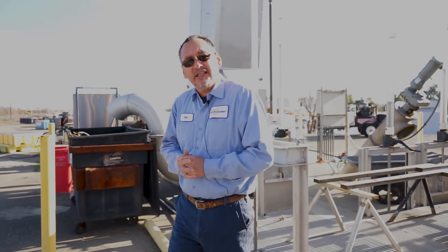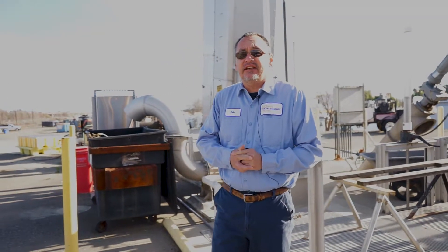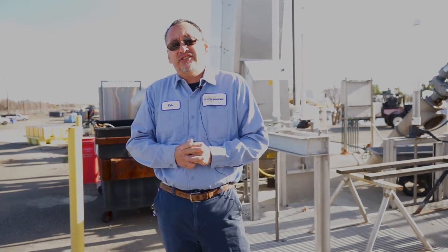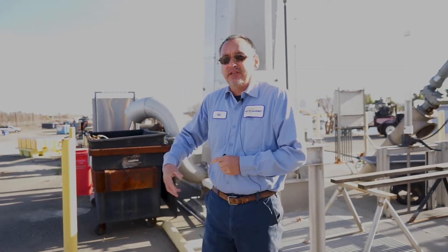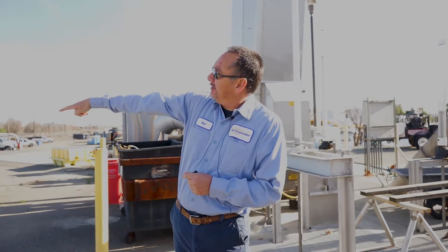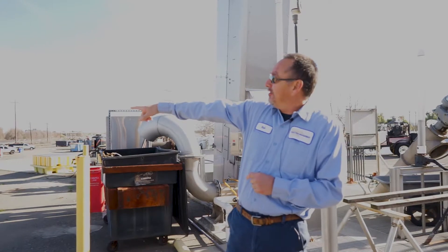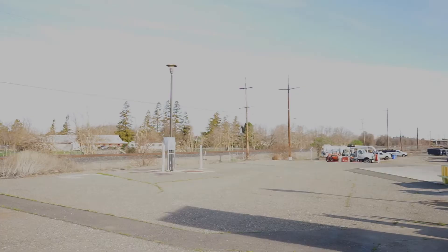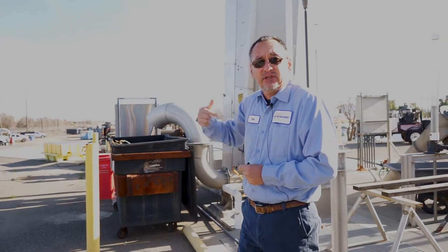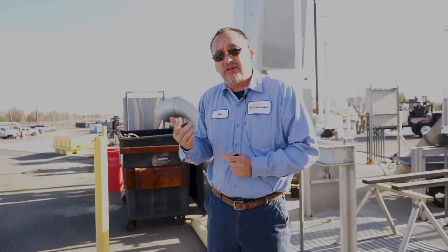How does the wastewater get from campus over to the wastewater treatment plant? We have an array of sanitary lift stations on campus and a bunch of gravity lines that feed what we call the influent pump station, which is next to the bargain barn. From there, it gets pumped down Old Davis Road, underneath the freeway, and diagonally underneath the railroad tracks up to underground near the lamppost. You'll see we have a little station — that's what we call a flow meter. It's measuring the flow instantaneously coming in from campus. We're required by state to measure both the influent and effluent flows on a 24-hour basis.